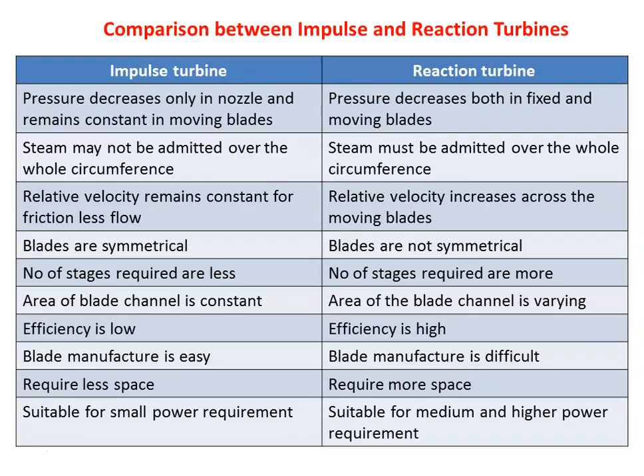Comparing impulse and reaction turbines: for the impulse turbine, pressure decreases only in the nozzle and remains constant in the moving blade; but in the reaction turbine, pressure decreases both in the fixed blade and the moving blade. In the impulse turbine, steam may not be admitted over the whole circumference because a jet of steam is produced by a nozzle. In the reaction turbine, steam must be admitted over the whole circumference. For frictionless flow in the impulse turbine, relative velocity remains constant: vr1 = vr2 (when k = 1); whereas in the reaction turbine, relative velocity increases across the moving blade, so vr2 is always greater than vr1.